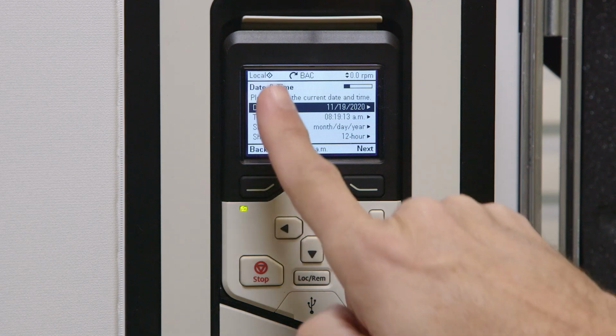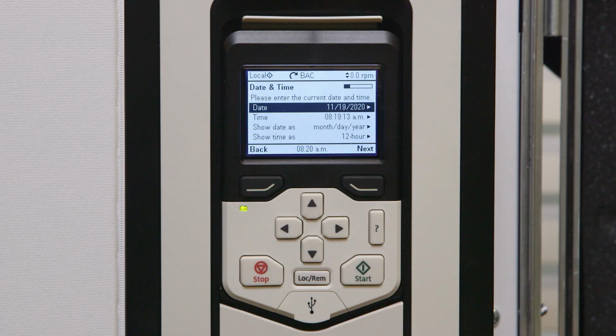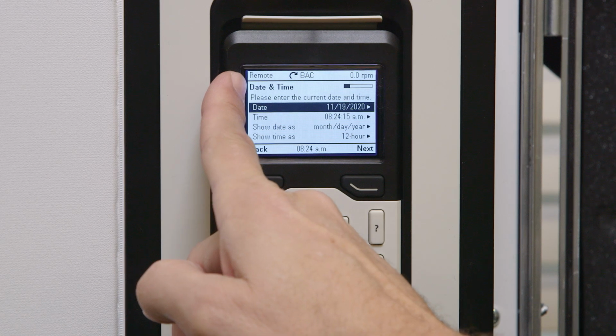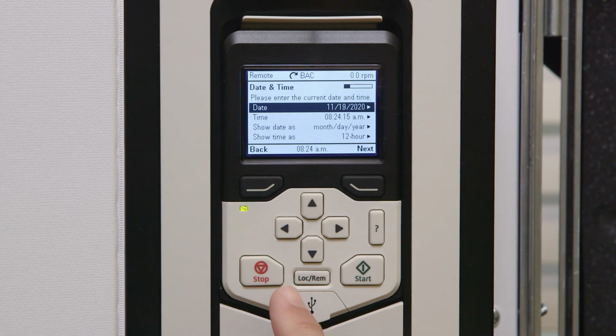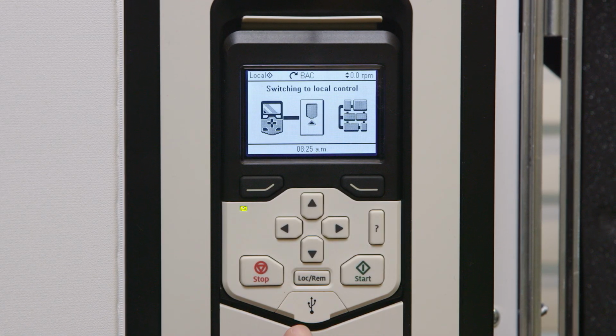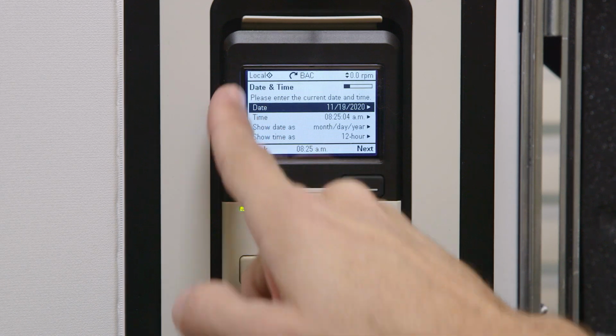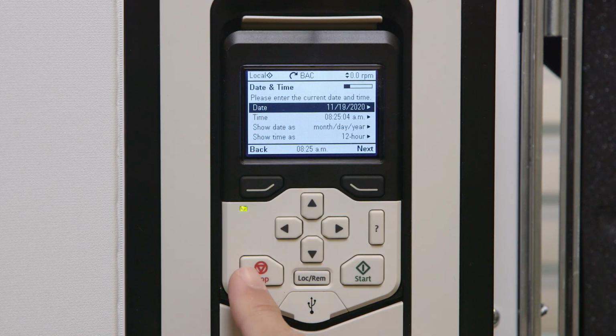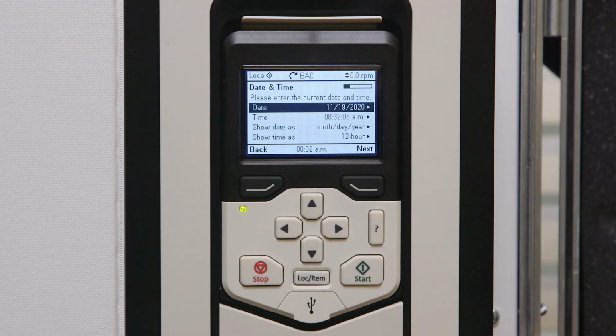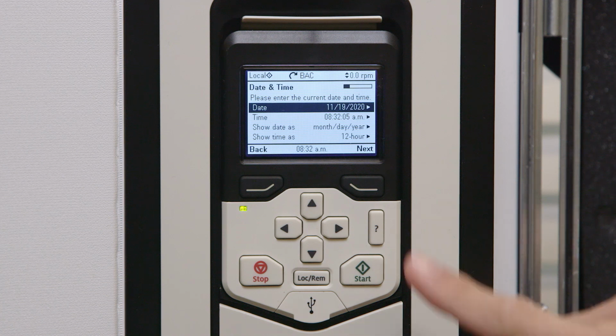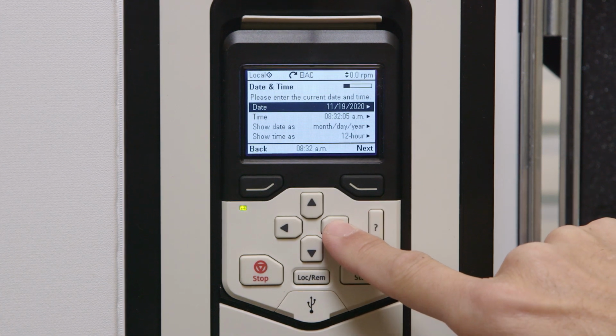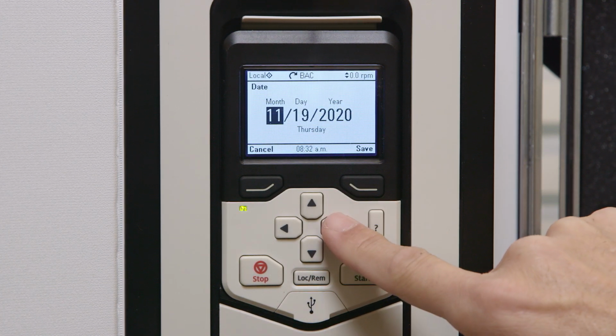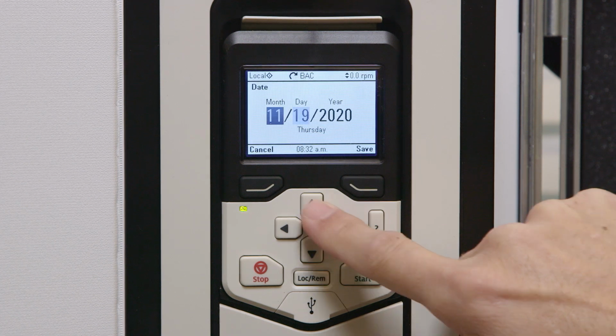Next, ensure the word Local appears on the screen. If the word Local does not appear, press Local Remote or LocRem button to get Local on screen. Once that is done, press the red Stop button. Now we're going to set the date and time. Continuing in the Start Setup mode, press the right arrow button on the keypad to adjust to the current date. Then press the right Soft button to save the date.